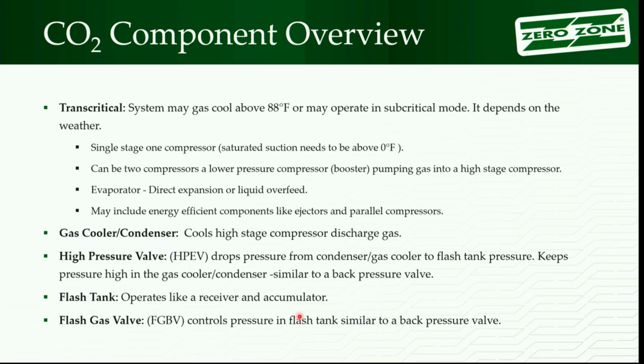If the receiver pressure, no valve, operates at the same pressure as the suction of the medium temp compressor, at the same pressure on the inlet of the expansion valve as I have on the outlet of the expansion valve, am I going to feed any liquid through the expansion valve? No feeding. So we need that valve there to generate a pressure differential to feed those expansion valves.